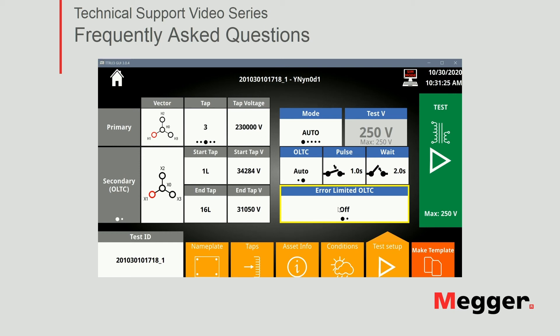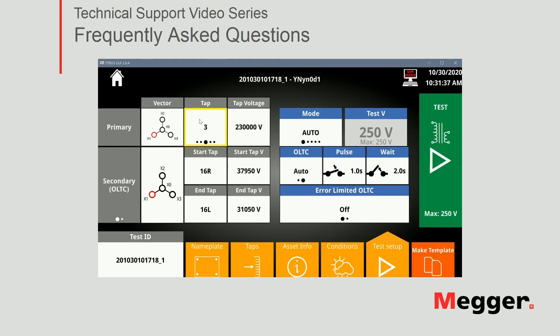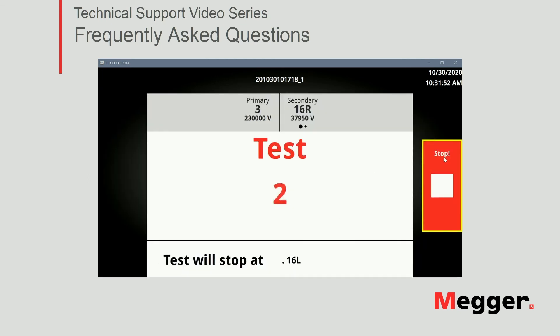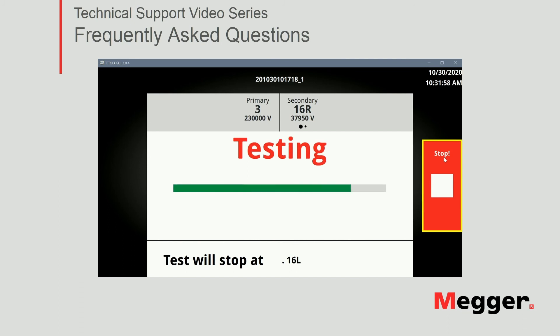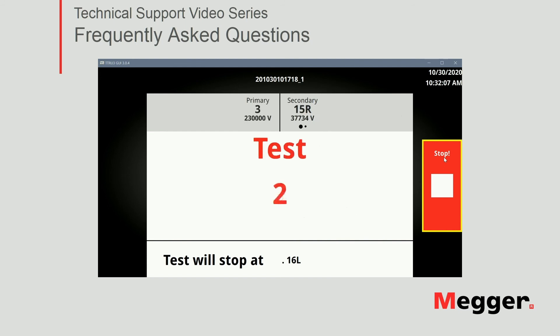So let's go ahead and press our play button. Just notice my initial tap is not the very first. So I'm going to test, I want to test all 33 positions from 16R to 16L, so I want to test all 33. So now I'm ready, I'm going to press play. So the unit goes into testing mode, it will perform the first test primary secondary and secondary 16R. It will automatically do my tap change and the wait and it will go to 15R and so on and so forth.